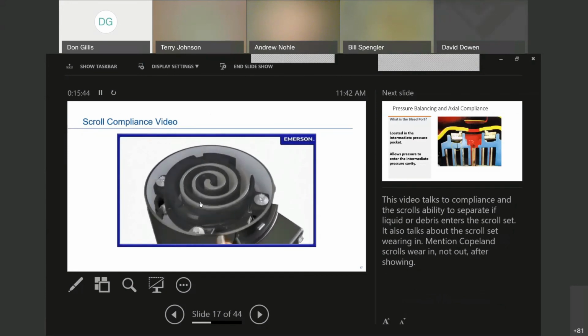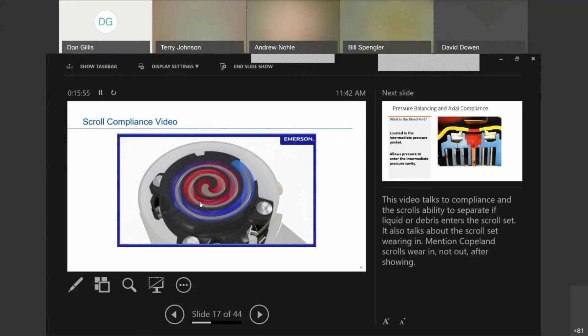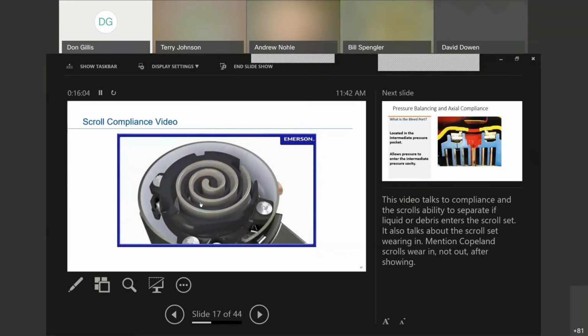During periods of cool weather, refrigerant can condense in the gas lines of HVAC systems, eventually migrating into the compressor. A key feature of the Copeland scroll compressor is its ability to handle liquid refrigerant with its compliant scroll design. During normal operation, radial contact between the two scrolls is held tight by centrifugal force, acting outward upon the orbiting scroll.